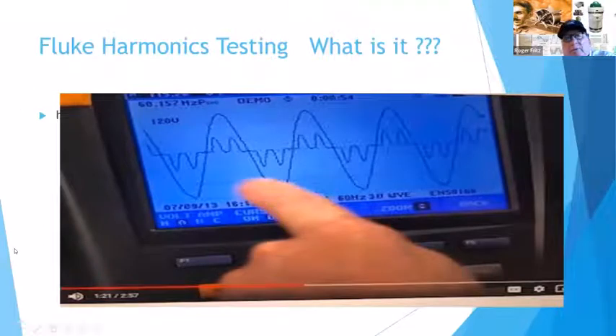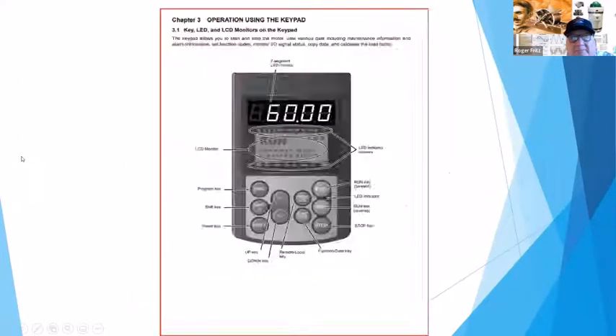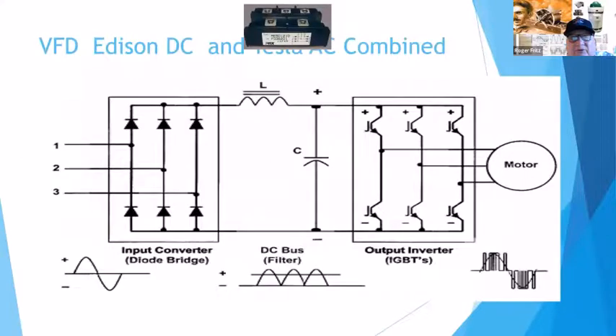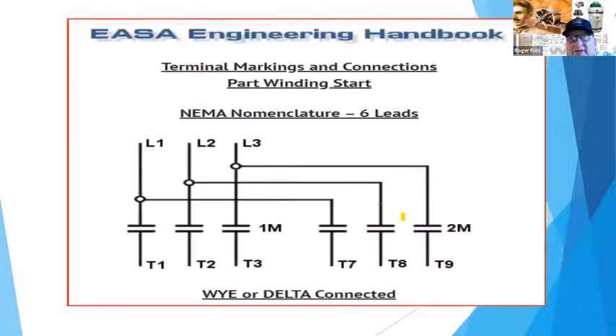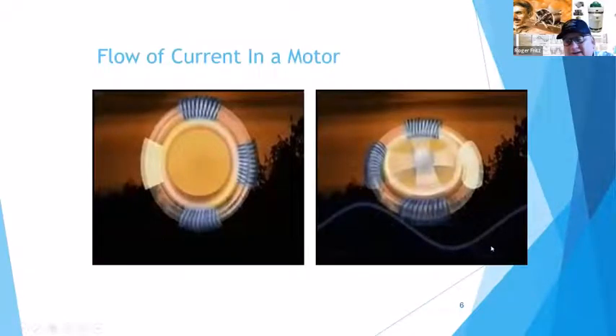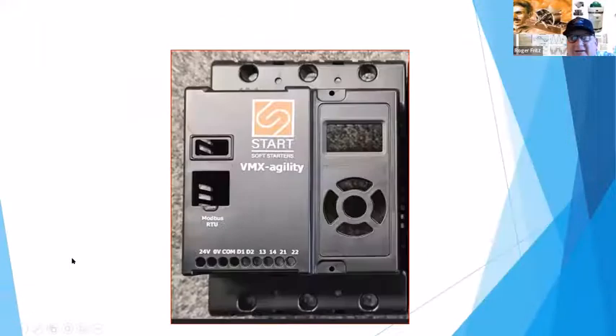Representative. So what actually happens is it allows you to go in and see that voltage form, that pulse that's going into drives. This can be either from a DC machine or an AC machine. So we can get back to the fundamentals of what is happening to that original waveform that Tesla was talking about. We're basically getting this off the generator. Well, what are we doing with it, and where are we driving it back to the motor? Motors like to be calm and peaceful, and that's where the life of the motor is dramatically changed.